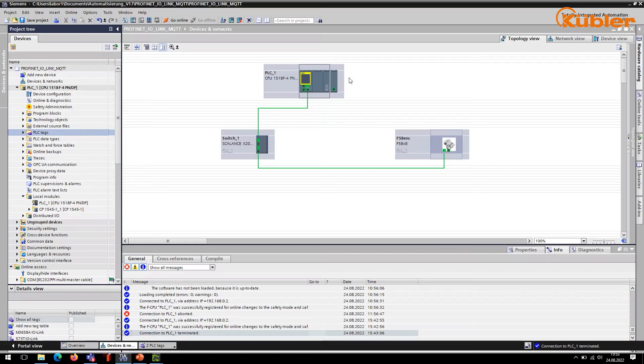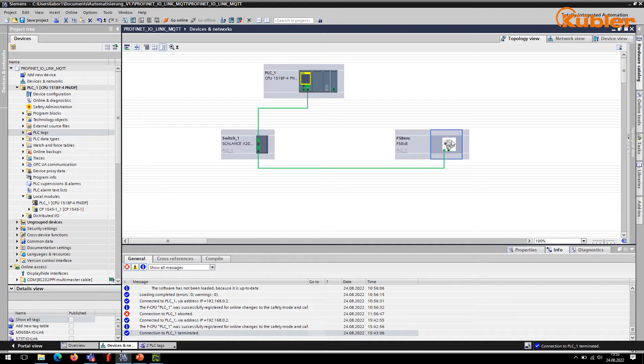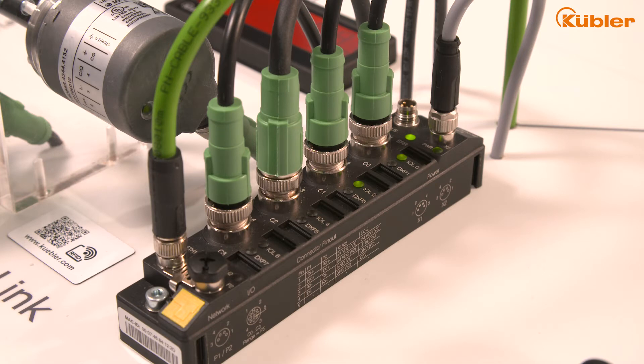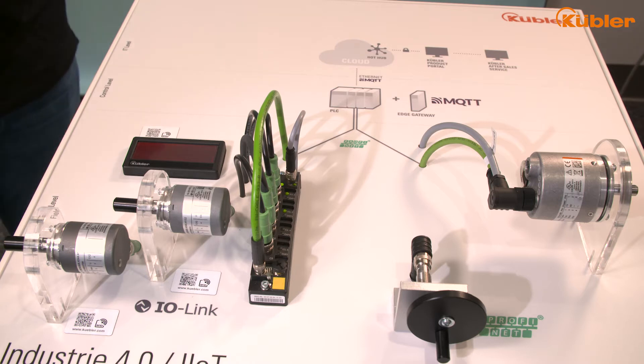In this project the PLC is already integrated and set up. We also have a F58 Profinet encoder in the network which brings this example closer to a real network situation. In order to be able to configure the IO-Link device of the IO-Link master, the IO-Link master must first be integrated into the Profinet network via the GSDML file.